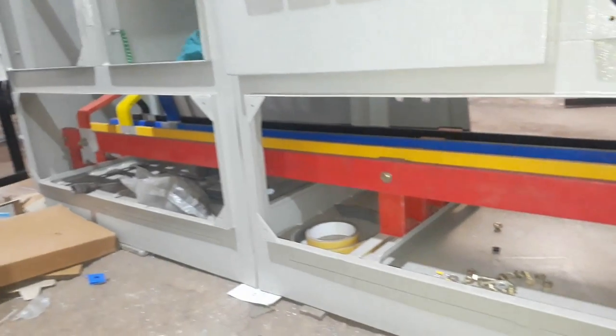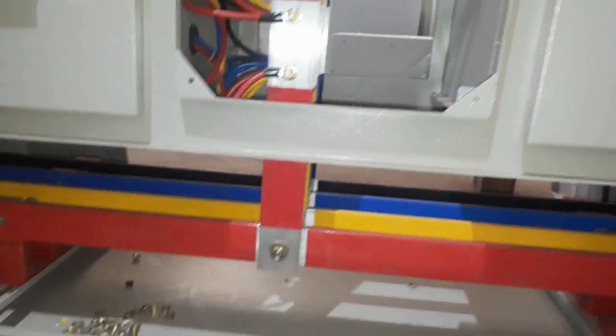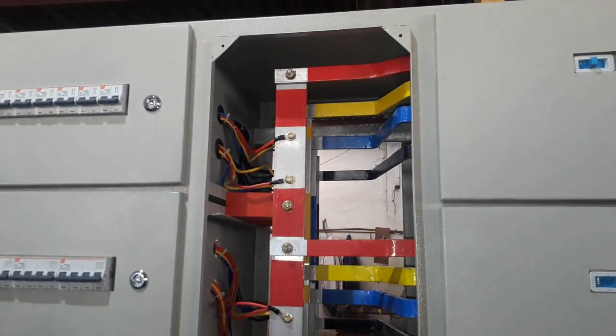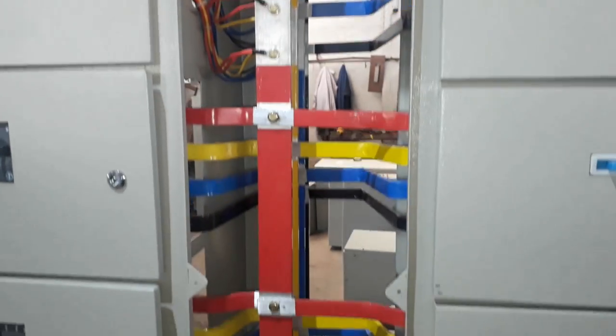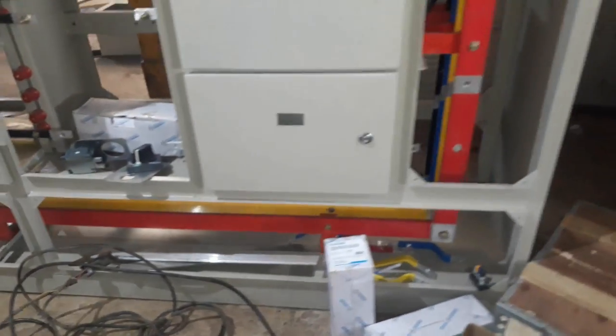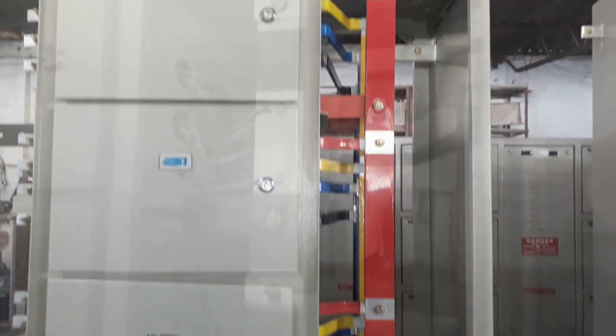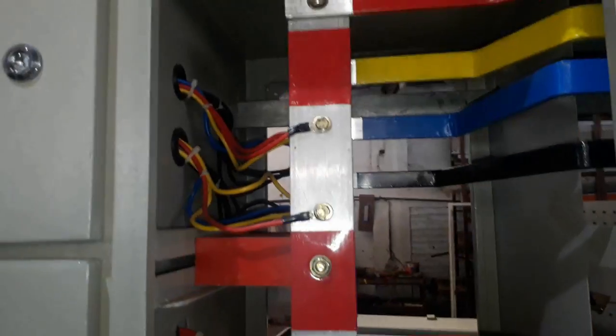Here you can see there is a T junction, and the bus bar chamber is present at the center of the panel, and the power is distributed to the left and right side circuit breakers with the help of cable as well as the bus bars. Also, there is a bus bar chamber at the extreme right of the panel, and there are also cable chambers.